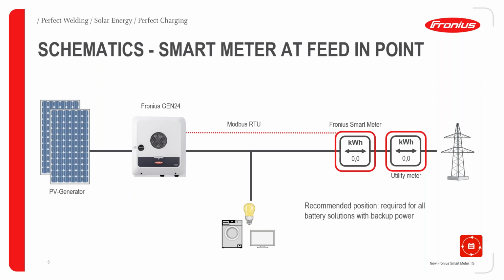It is mandatory to put the smart meter, the primary smart meter, in the feed-in point for all the battery solutions with backup power, because it has to tell the inverter whenever there is excess energy flowing from the grid that now the battery has to discharge the power to supply the load. So that's how it's charging and discharging the battery.